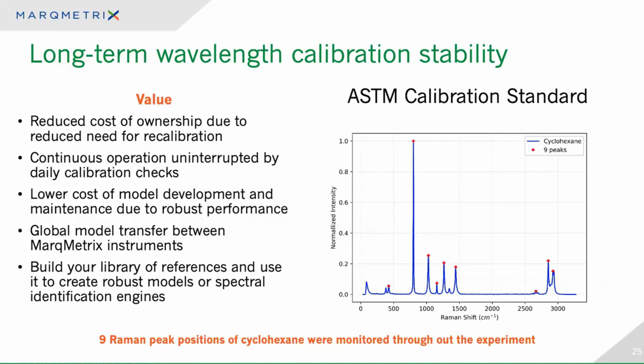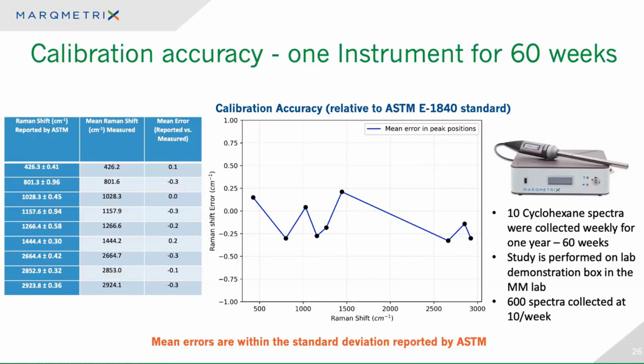Here's the calibration data for 60 weeks. We take 10 cyclohexane spectra every Monday that it's back in the office. We use this data in our calibration accuracy analysis, and you can see the 9 peaks on the left, the mean error reported over the last 60 weeks across those individual points. This is interesting data, but I like this slide better. So that's all 600 spectra from the beginning of our calibration study overlaid. Every spectrum we collected over the last 60 weeks is sitting there, all 600 of them, and you can see the reproducibility at those 9 ASTM points graphically on the right.